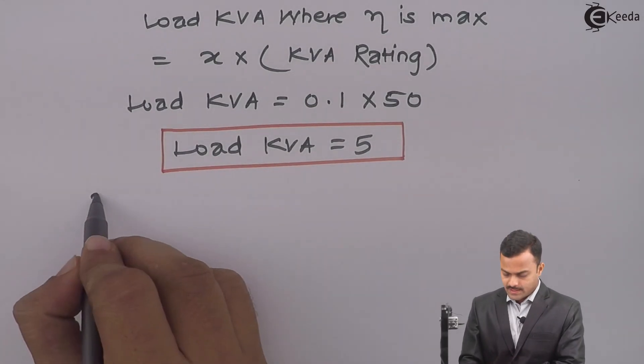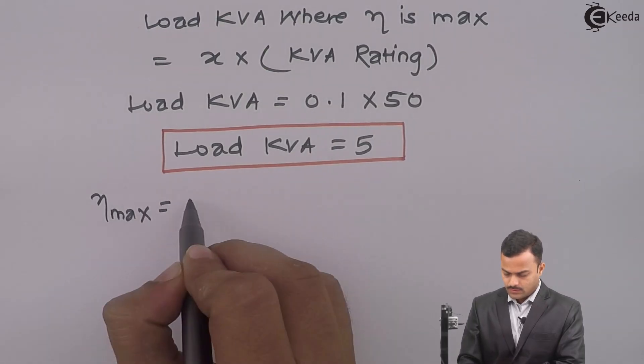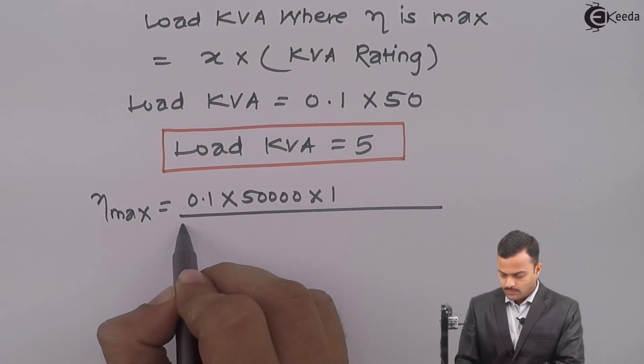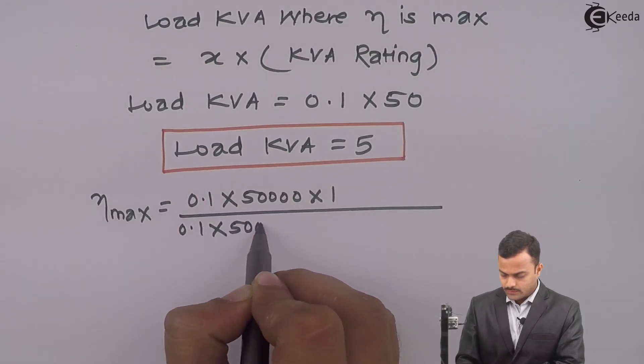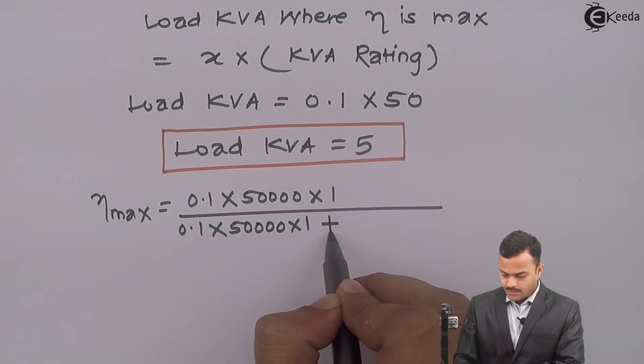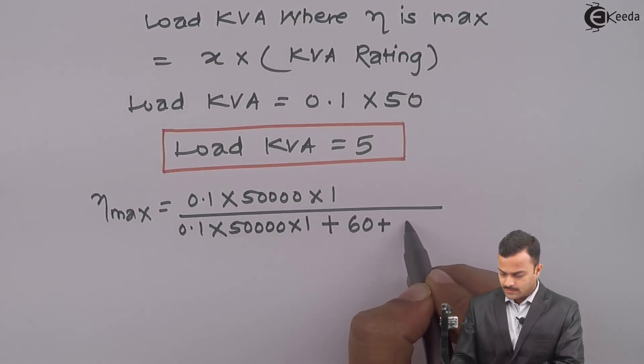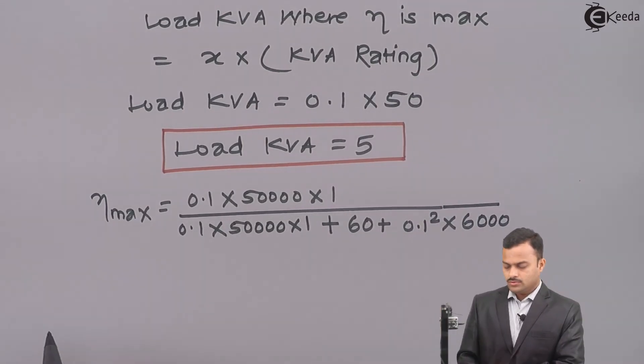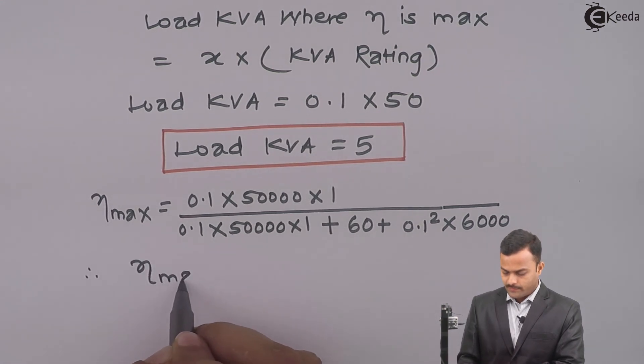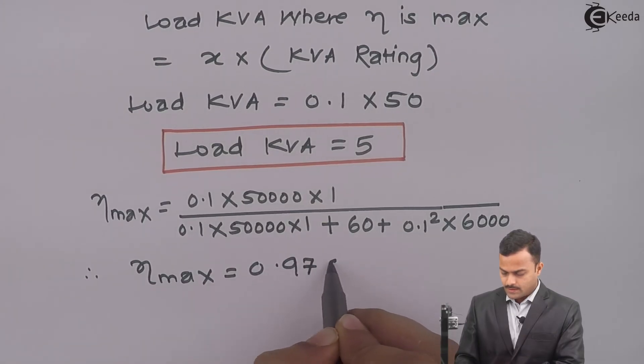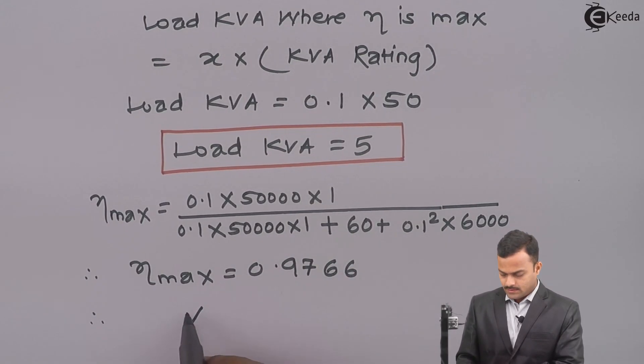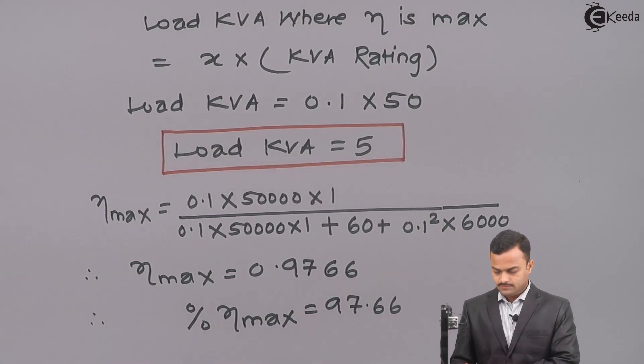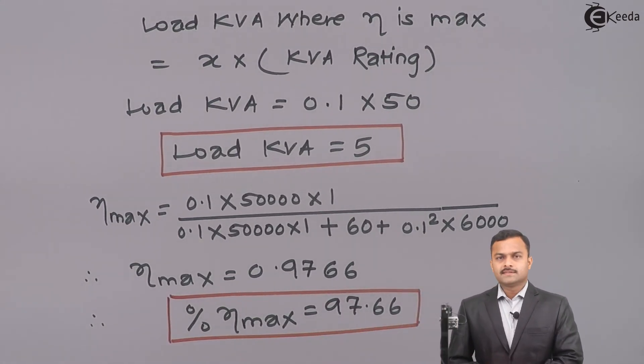Now maximum efficiency equals 0.1 multiplied by 50,000 multiplied by 1 upon 0.1 into 50,000 multiplied by 1 plus iron loss 60 plus 0.1 square and full load copper loss 6000. If you solve, maximum efficiency equals 0.9766, in percentage 97.66%.